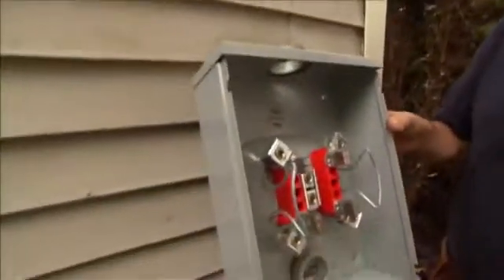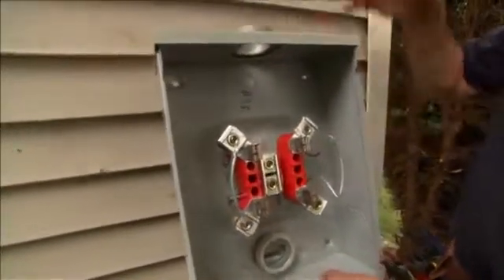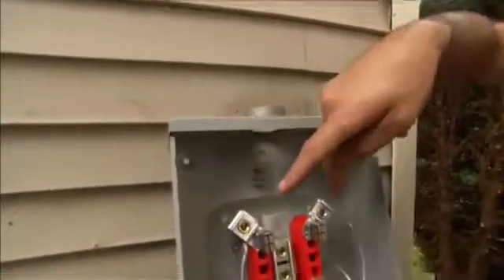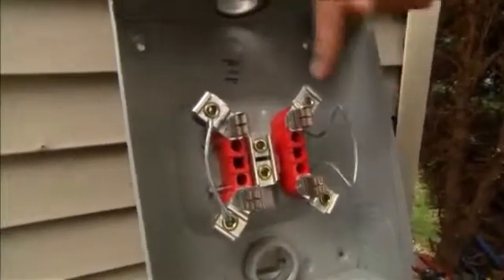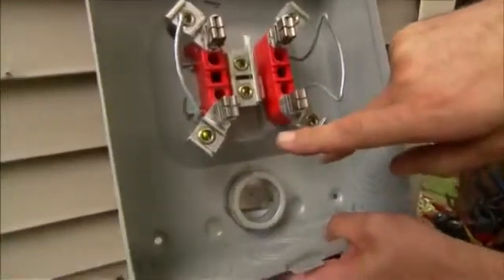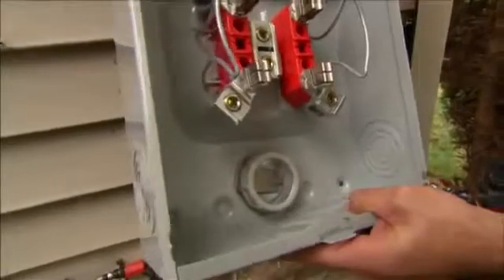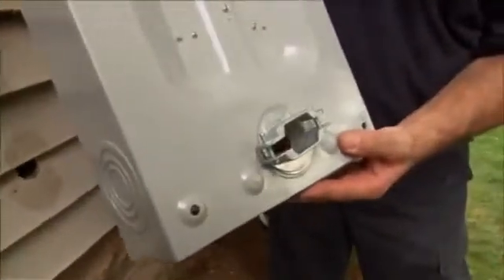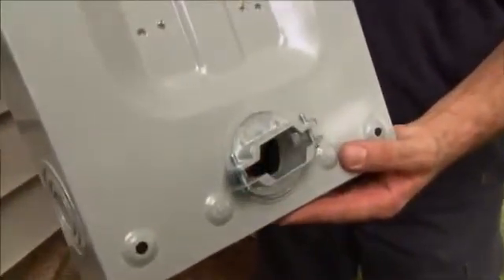Now this is your new meter socket, rated for 200 amps. The power comes in through the top, ties onto these two terminals, goes through the meter, comes out on the bottom two terminals, and then goes through this hole. On the back, there's a connector that holds the wire going into your house.